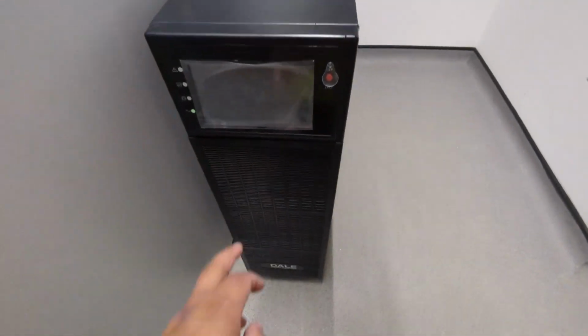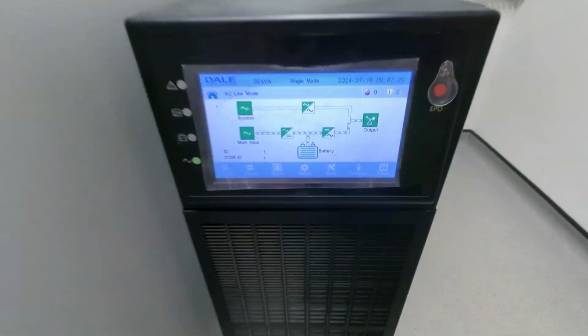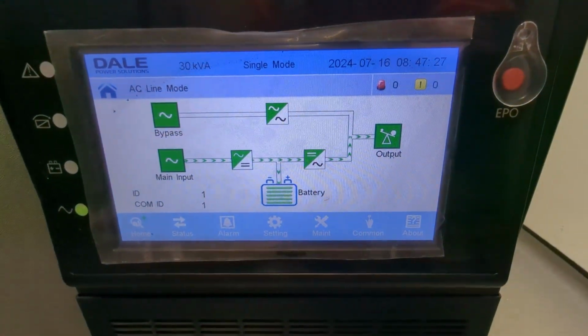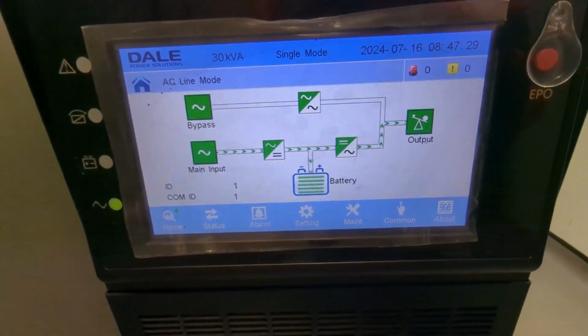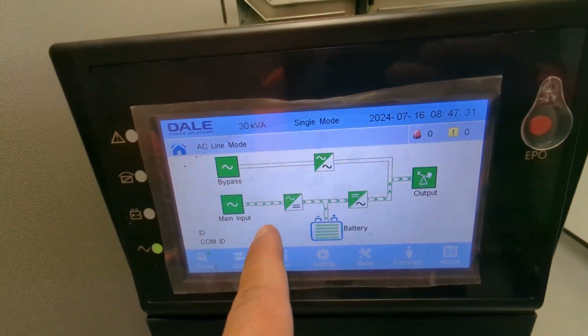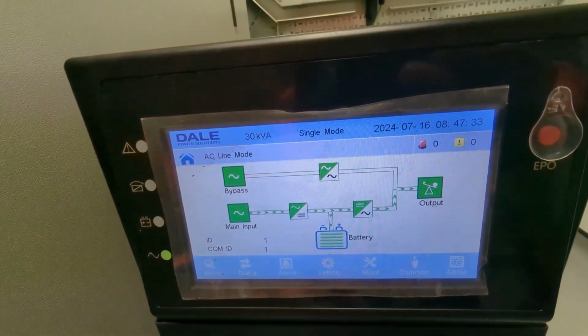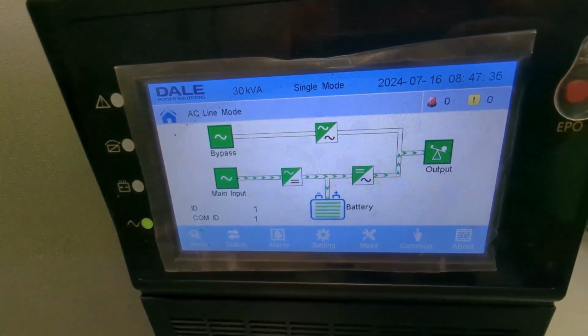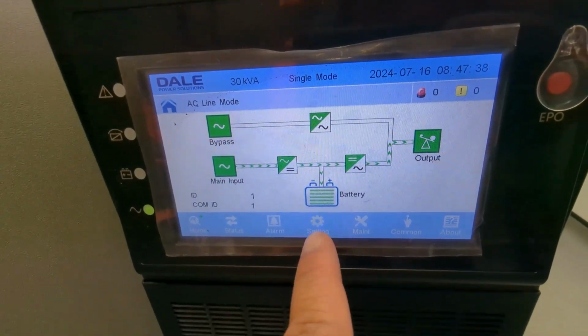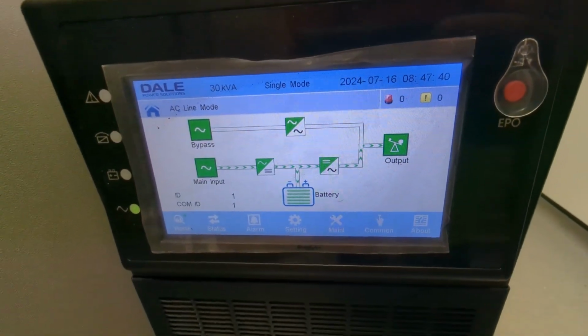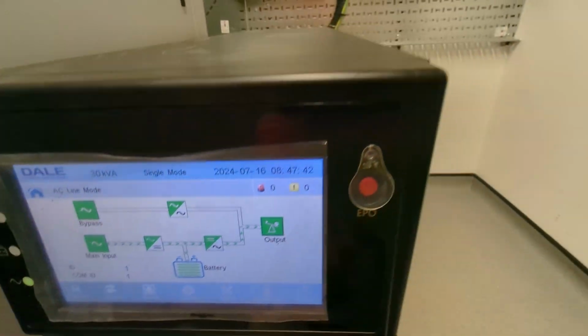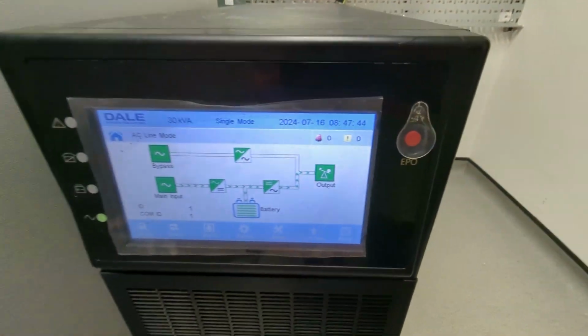And then you've got this thing here, which is this really nice UPS controller. So there you can see currently our incoming is on, the UPS switch is on, it's supplying to the battery, and the battery is feeding the building. So right now, if I press this button and turn off the UPS...